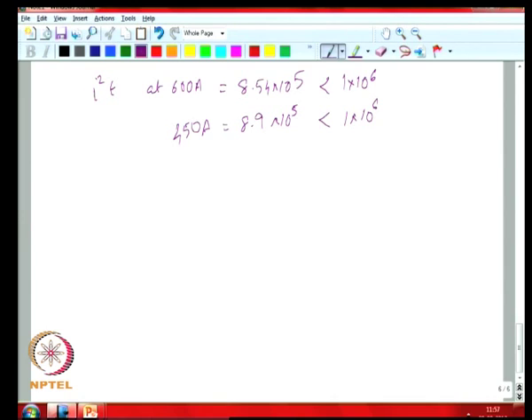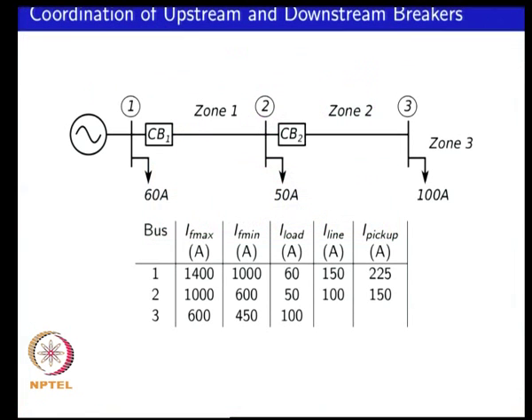In many situations, it may not be possible to obtain all the conditions required. If you have overlapping ranges of fault current levels, you may not be able to achieve all coordination requirements. Also, your upstream source impedances may vary over a wide range — transformers switching in and out, lines tripping — so impedances may vary widely. Over that entire range, it might not be possible to achieve full coordination; your objective is to meet as many requirements as possible.